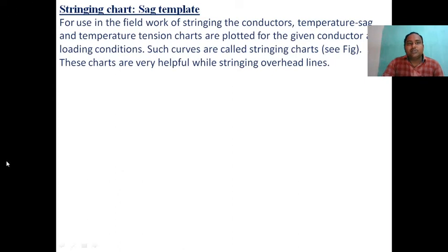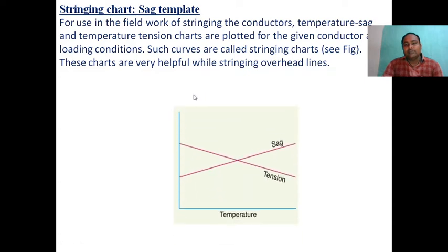Stringing chart, sag template. What is the stringing chart? For use in the field work of stringing the conductors, meaning erection of the conductors, temperature-sag and temperature-tension charts are plotted for the given conductor and loading condition. Such curves are called stringing charts. These charts are very helpful while stringing overhead lines.